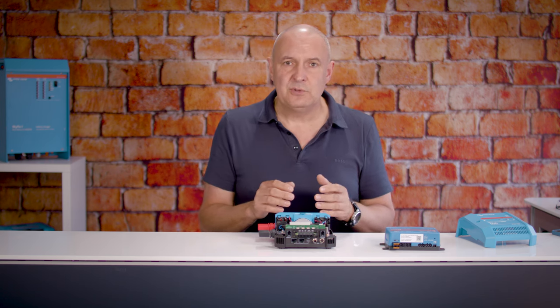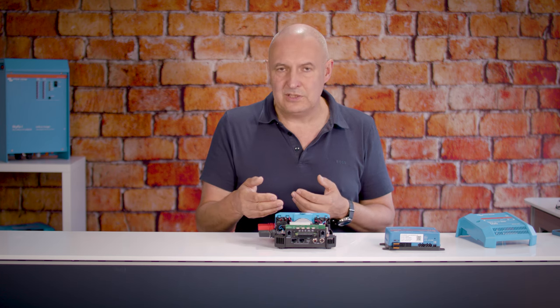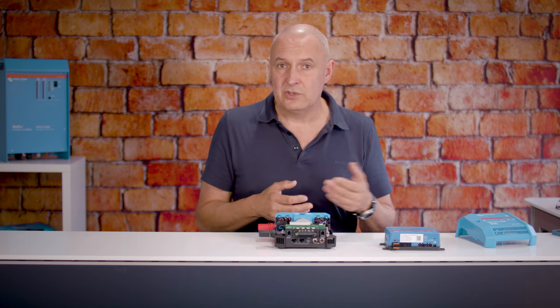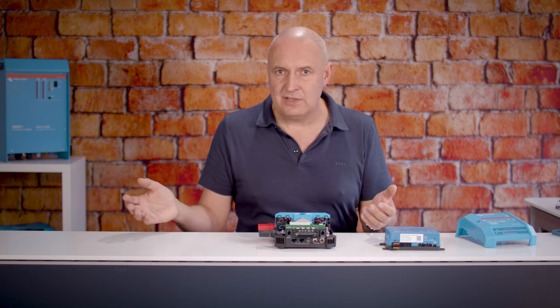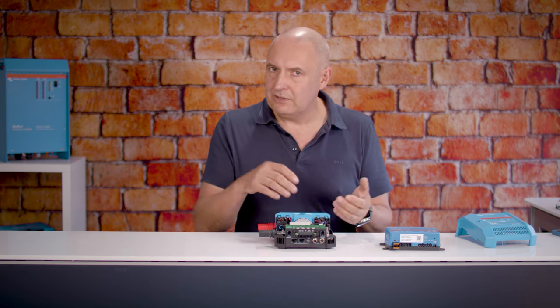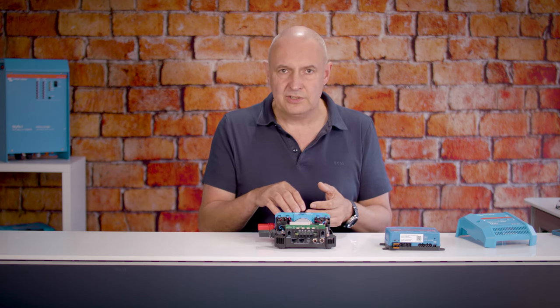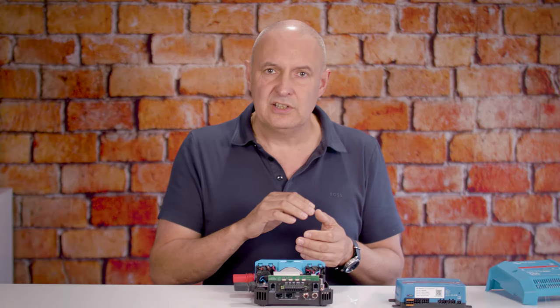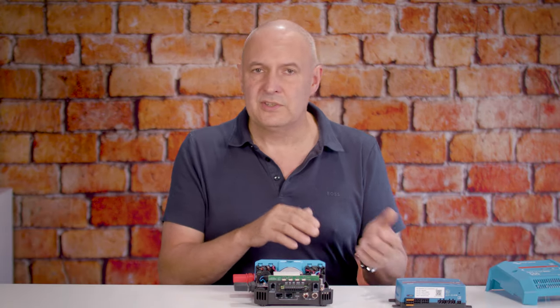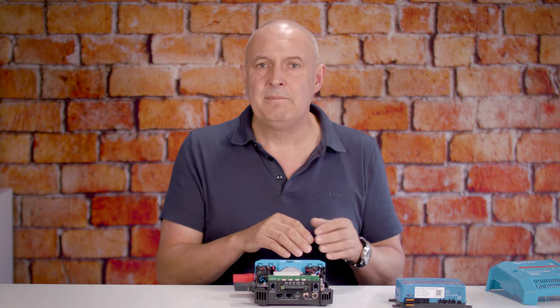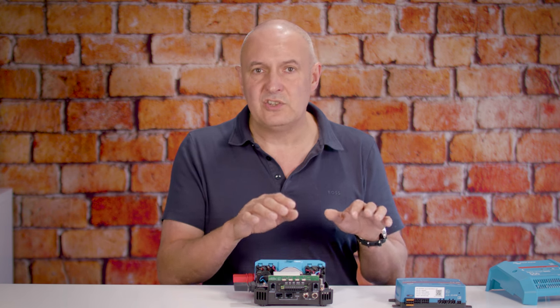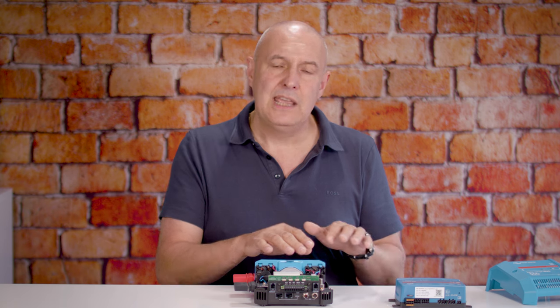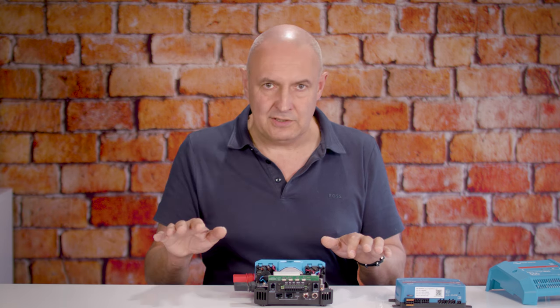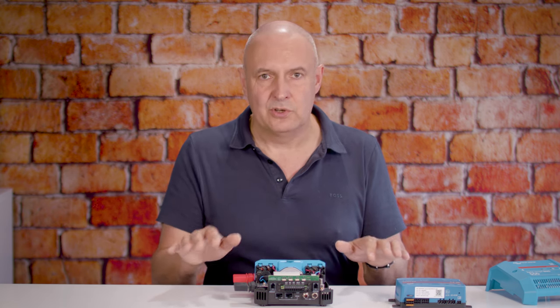off. So we can have a situation, for instance, where we're charging at 20 amps, but we've got 10 amps worth of loads, 10 amps therefore going into the battery. The battery communicates that it doesn't want to be charged at the moment. Rather than just turning the charging source off and flipping ourselves into a discharge situation, DVCC will set the charging current to 10 amps in order to match the loads and still satisfy the battery's requirement not to be charged.